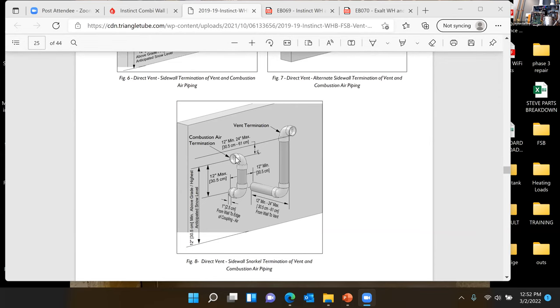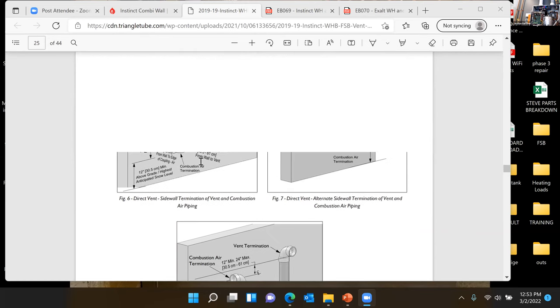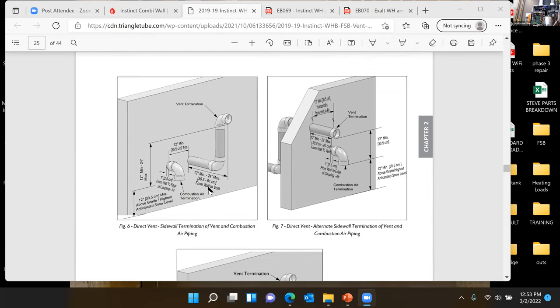So the intake is always going to be 90 down, depending on if you have to get this up over the snow level or if you have something down here. But just note that you have to terminate it and 90 it down just like this. So it shows that 1 inch off the wall, we can have that intake right up tight against the wall. Then minimally, we need 12 inches of separation side to side, and we need 12 inches of separation from the face of this 90 to the bottom of this 90.